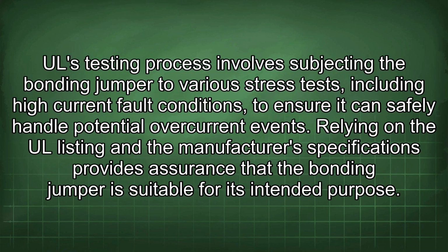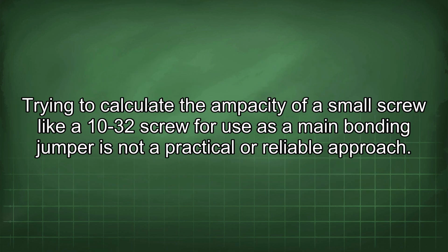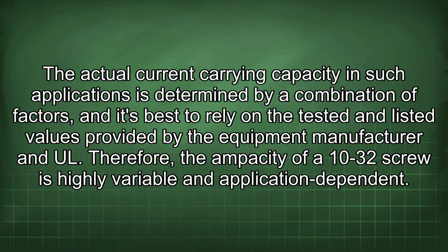The UL testing process involves subjecting the bonding jumper to various stress tests, including high current fault conditions, to ensure it can safely handle potential overcurrent events. Relying on the UL listing and the manufacturer's specifications provides assurance that the bonding jumper is suitable for its intended purpose. Trying to calculate the ampacity of a small screw like a 10-32 screw for use as a main bonding jumper is not a practical or reliable approach. The actual current carrying capacity in such applications is determined by a combination of factors, and it's best to rely on the tested and listed values provided by the equipment manufacturer and UL.